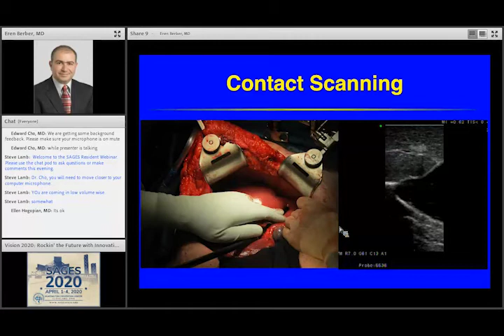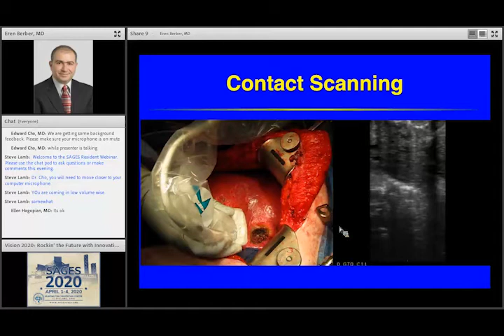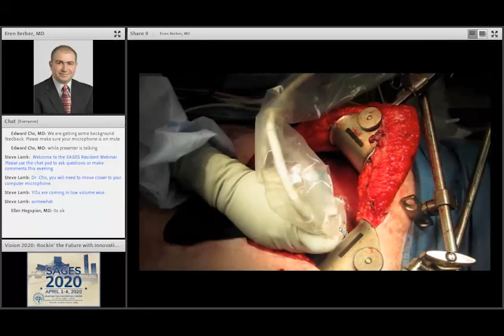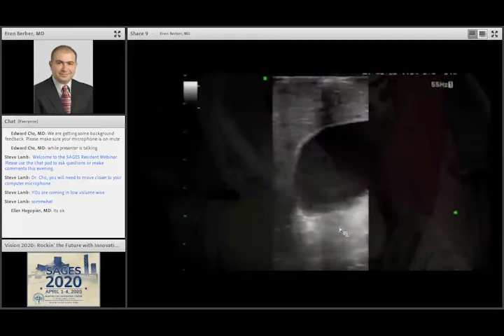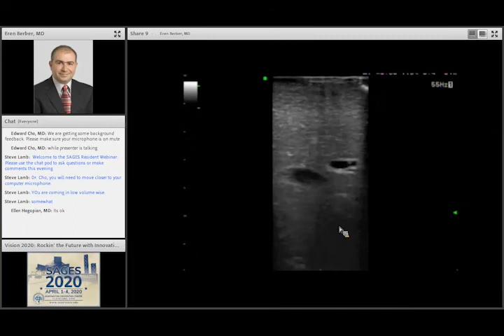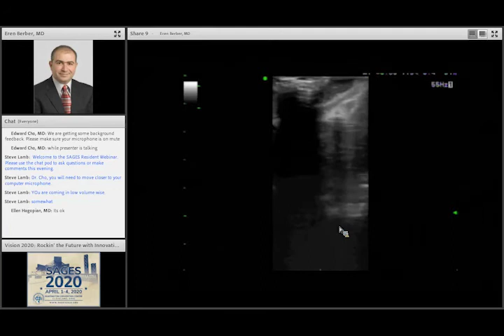This is another view of contact scanning where you have one of the ultrasound probes I showed you. You just use a sterile ultrasound cover. You want to make sure that you place some ultrasound gel inside the cover so you can use any of the external transducer on the liver. And this is showing the video about the contact scanning. But you'll see that one of the drawbacks is going to be if you don't have a good contact, like you've done some resections and you're looking at the resection bed, then you will get into some artifacts. That's when the standoff scanning technique becomes handy.